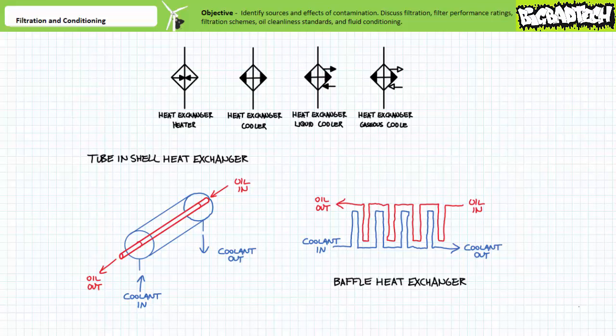Finally, note that the reservoir itself can be considered a fluid conditioning apparatus. Not only does the reservoir ensure a quantity of oil is readily available to the system, it also serves to cool liquid returning from the system and allow time for any particles to settle out and any entrained air to dissipate before the oil is again pumped up and circulated through the system. We'll examine reservoirs and hydraulic power units in greater detail in later lectures.